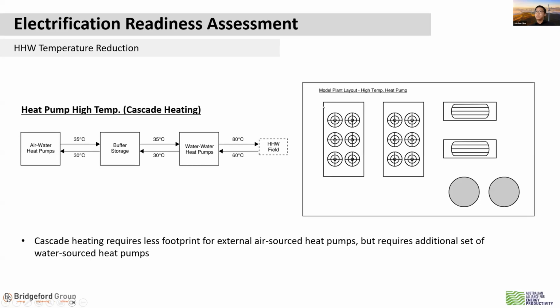Now, if you're not able to lower it down to, say, 50 or 60 degrees, and have to maintain 75 or 80 degrees, what you end up needing when designing a heat pump system for these high temperatures is a separate set of water-to-water heat pumps, or so-called water source heat pumps, which are the two smaller units just next to the larger air source units there, to bring the temperature supplied by these lower temperature heat pumps up to the temperature you need. The point is that if you want higher temperature heating, this type of cascade configuration may be necessary. And while the air source heat pump takes up less space compared to the previous photo, overall your footprint requirement goes up. Because you have more units, it's more expensive to implement too, and it's also less efficient.